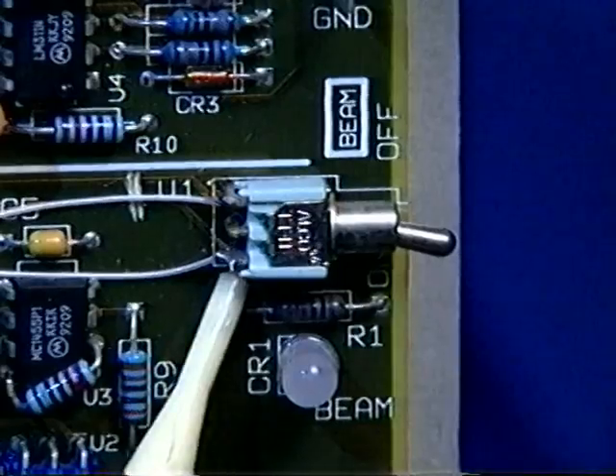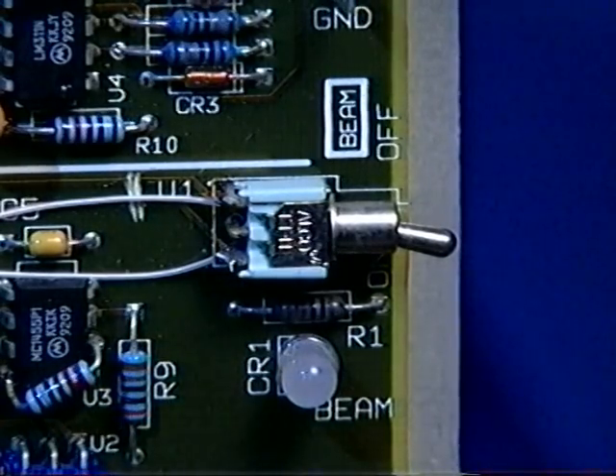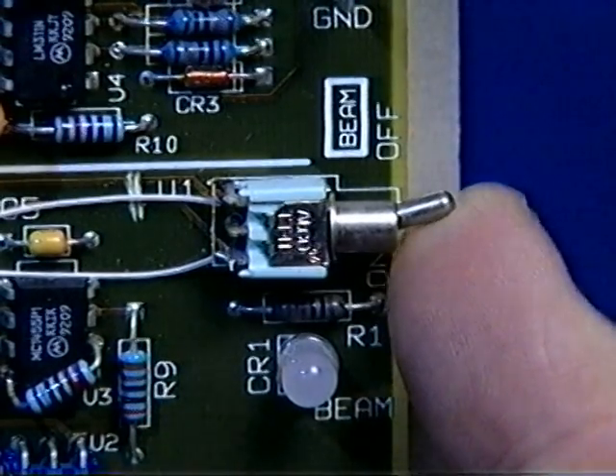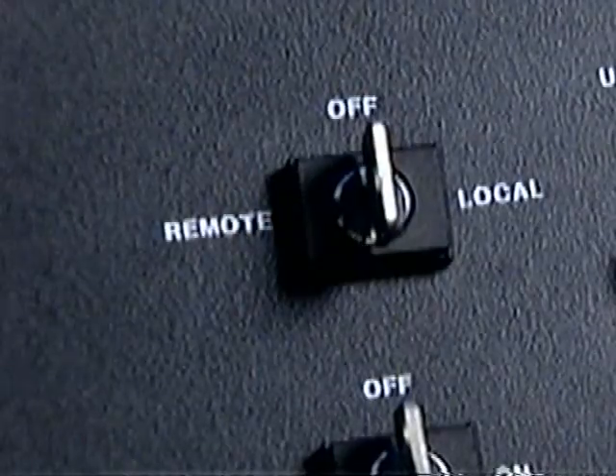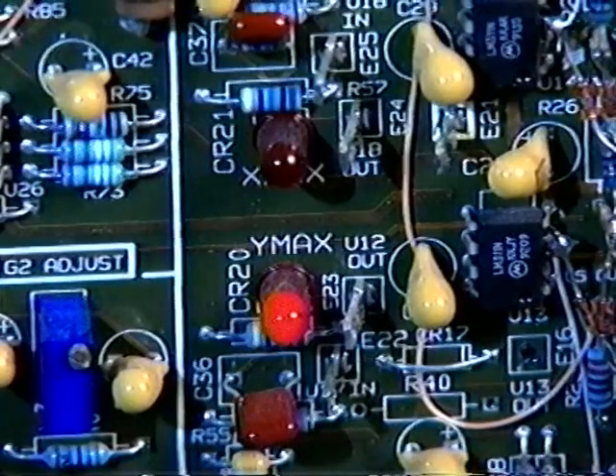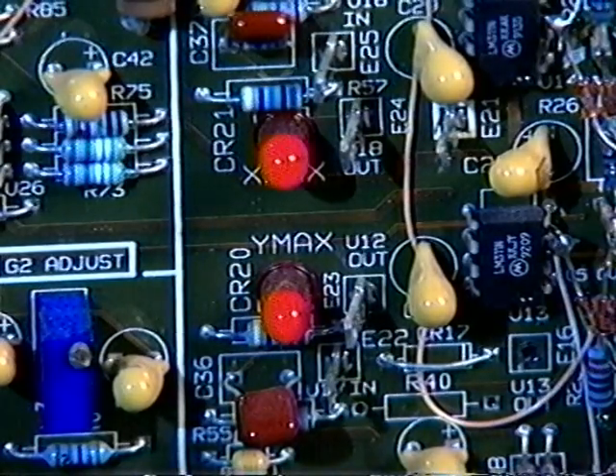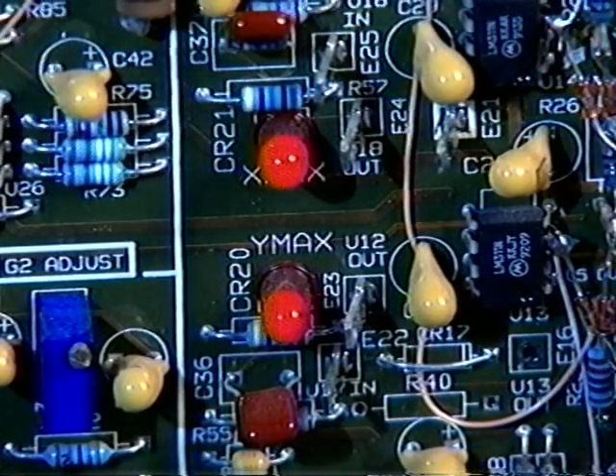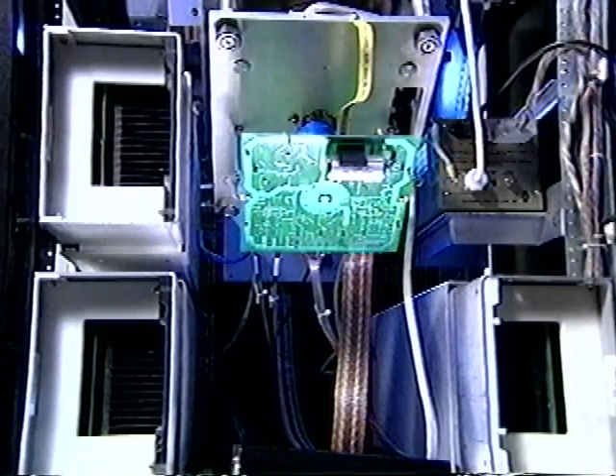Set the beam switch to the off position. The beam switch is used to enable or disable the G2 voltage. Turn the projector mode switch to local. The projector should power up immediately. Ignore the red X max and Y max LEDs on the correction card. Open the lens cover by pressing the lens button on the power drawer. Verify that no light is visible in the projector's lens. Allow the projector to run for a minimum of 2 hours.